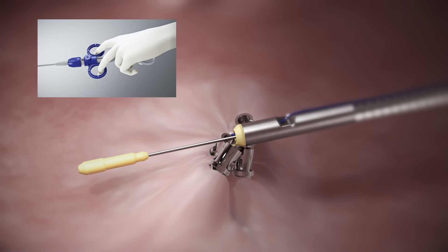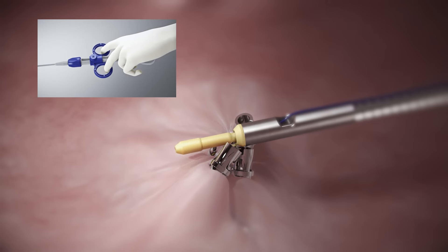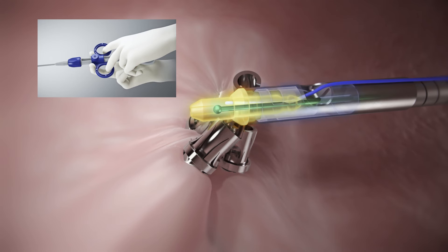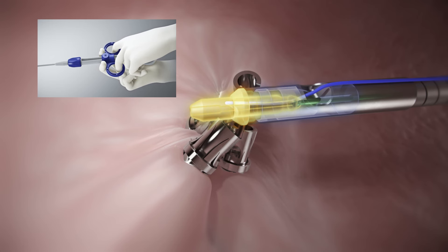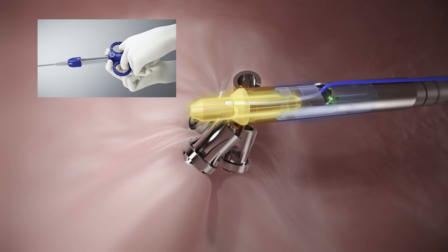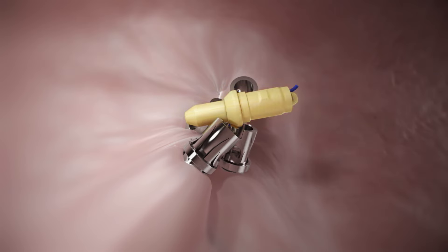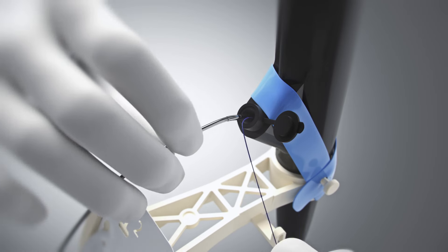Squeeze the cinch handle with one hand to pull the PEEK plug into the PEEK collar and lock the suture. Stage 2 of deploying the cinch will require two hands. Continue to squeeze the cinch handle to advance the beaded rod through the PEEK plug. Finally, continue to squeeze the handle to activate the suture cutter and release the PEEK collar and plug. Remove the cinch and remaining suture from the scope channel.